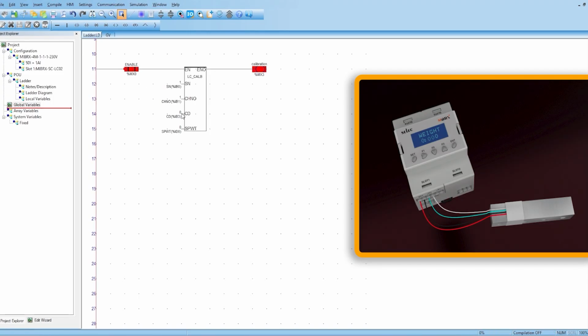Next, we perform span calibration. Place a known weight, for example, 1 kg, on the load cell. Change calibration code as 1. Set span weight as 1000 in grams. Now, trigger the calibration again. When calibration bit is on, then only known weight calibration is done. Once the calibration is triggered, the calibration data gets stored in the PLC, the system will now display the correct calibrated weight value.